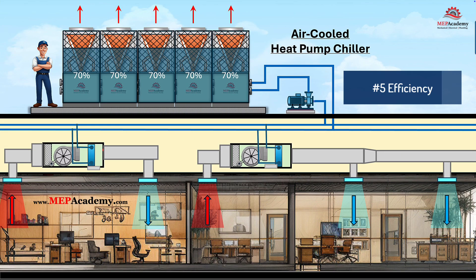5. Efficiency and Part Load Operation. Efficiency is a cornerstone of these modular air-to-water heat pump chillers, particularly when multiple units operate at part load. Inverter-driven compressors and variable speed fans allow each module to adjust its output — e.g., 15 to 100% capacity — based on real-time demand, optimizing energy use during off-peak conditions. A system with several modules can stage operation, running fewer units at higher efficiency or distributing load across multiple units at lower capacities, reducing overall energy consumption compared to a single oversized chiller running at partial load. This part load efficiency is especially beneficial in buildings with fluctuating occupancy or seasonal variations, where maintaining comfort without waste is key.